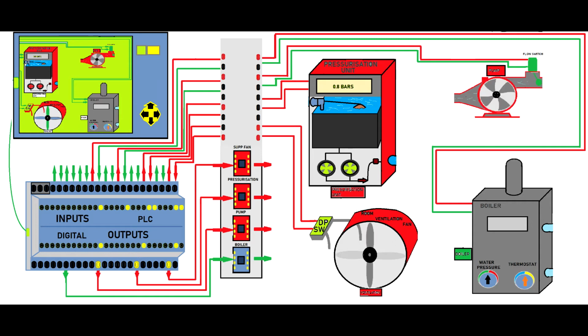We all know that the pumps which circulate the heating agent to the system will have a flow switch, and that flow switch must be activated to send back the information to the programmable logic control. As you see in this picture, the pump is running and it just sent back the information. So now the HMI shows the status of the heating pump as running. With the heating agent pump running, the last thing to do is to start the boiler. That's the last part. And the boiler starts, and you will get back instant information if it's healthy or not.